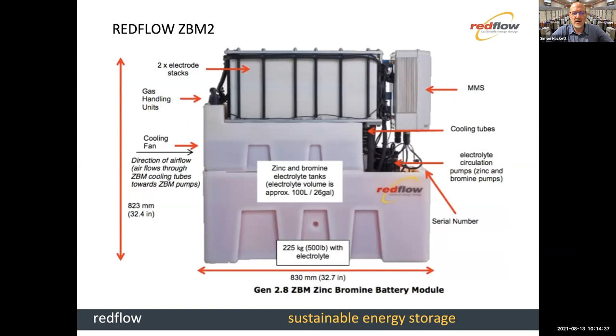So what happens is when you want to charge this battery, the zinc that's in the fluid comes out of the fluid and is plated in very thin layers on top of a conductive plastic membrane, so the zinc is electroplated inside that stack. When it's time to pull energy out of the battery, it acts just like an ordinary battery when you're discharging it: the zinc goes back into solution in the process of that discharge. By the time the battery is completely empty, all of the zinc has gone completely off those plates again. That's actually the secret to the long life of these devices, which is that when you completely discharge it, all the zinc comes off the plates and you've got a new battery again.